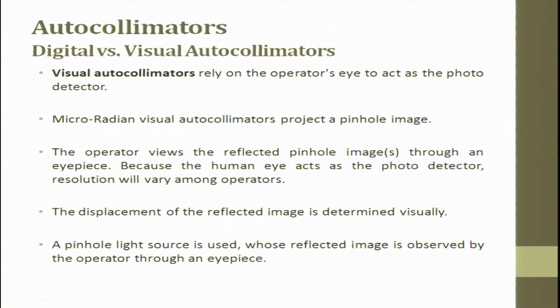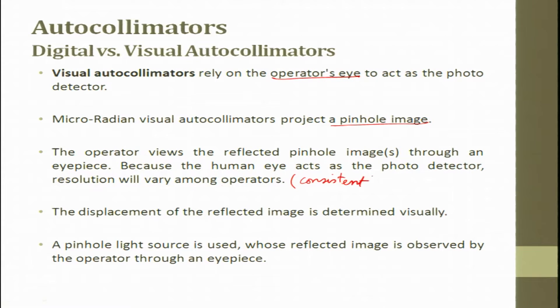The visual autocollimator relies totally on the operator's eye. The micro-radian visual autocollimator projects a pinhole image, and the operator views the reflected pinhole image through an eyepiece. Because the human eye acts as a photodetector, the resolution will vary from operator to operator — it is not consistent. Measurements are in microns or less than microns, or in radians or micro-radians when talking about angular values.